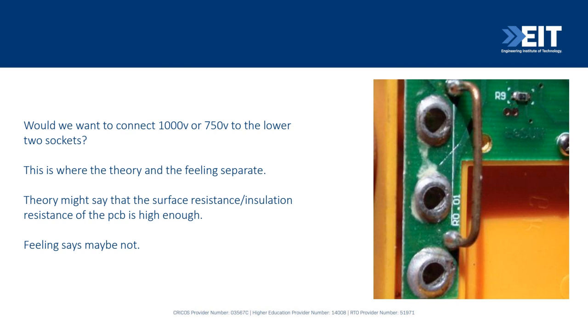But now have a look here. It means the negative terminal of this meter is effectively connected to this socket, which is maybe 10 millimeters away from the positive socket. At some point this particular meter got damp, had some water in it - you see this corrosion on the board. The bare board by itself can maybe withstand 1,000 volts between these two terminals, but with corrosion on it, that's why I don't put 1,000 volts on a meter like this. You don't know what's happening inside.